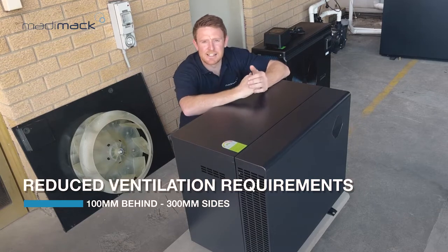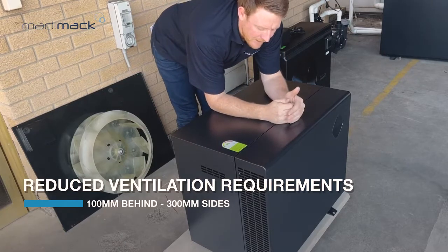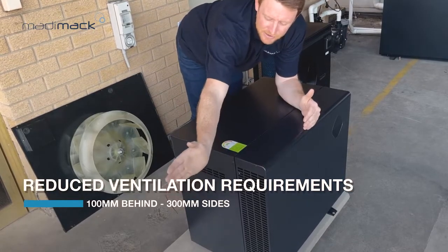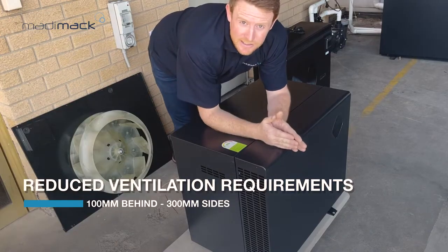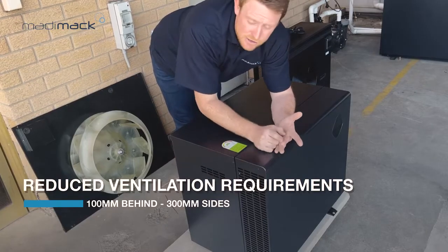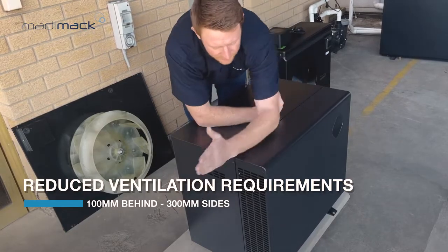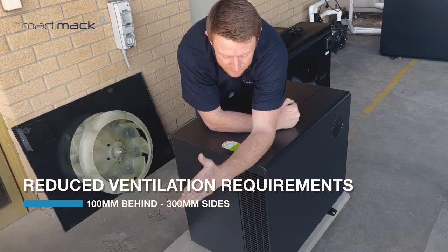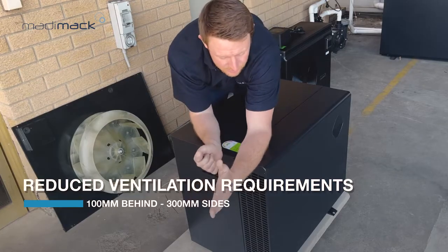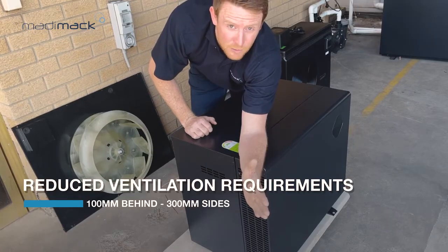It's the first of its kind, a side premium airflow. So not only have we introduced the centrifugal fan, which is spinning here and pushes the air in a sideways direction, but obviously upon installing a heater, you can usually expect to have either an acoustic box, a filter, or even just a pump being in the way, which could be sitting next to the unit. So what we've actually done, instead of having a singular 90-degree angle, is introduce a deflection system within the unit, which pushes the air at a 45-degree forward angular direction.